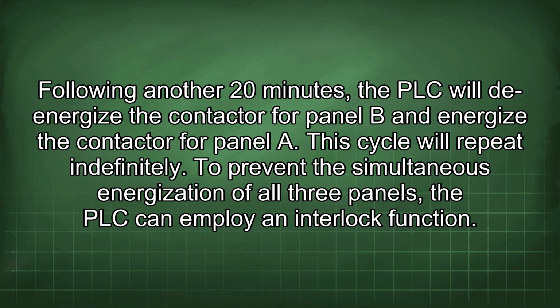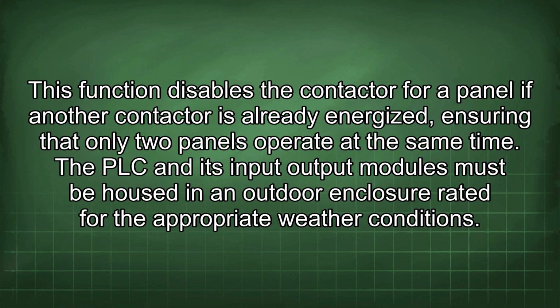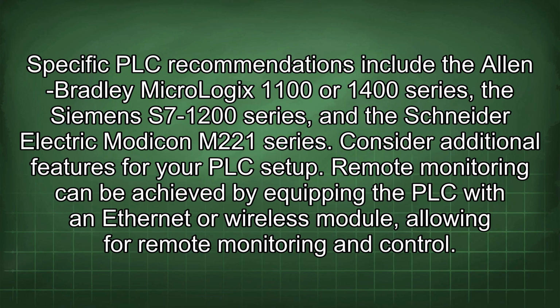To prevent the simultaneous energization of all 3 panels, the PLC can employ an interlock function. This function disables the contactor for a panel if another contactor is already energized, ensuring that only 2 panels operate at the same time. The PLC and its input-output modules must be housed in an outdoor enclosure rated for the appropriate weather conditions. Specific PLC recommendations include the Allen Bradley Micrologix 1100 or 1400 series, the Siemens S7-1200 series, and the Schneider Electric Modicon M221 series.